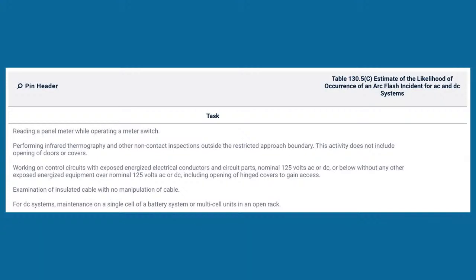Okay, let me answer that for you. Now, what happened is when we put the tables in, that was mainly for contractors. You go to big facilities, they're performing all their arc flash calculations for all their equipment. And I actually went out to Nucor Steel in Seattle. They had actually come to one of the NFPA classes that I was doing on 70E, and I told them some of the software being used at that time wasn't taking into consideration some of the parameters that were in the tables, and therefore some of the hazard risk categories they were coming up with on some of that equipment were wrong.